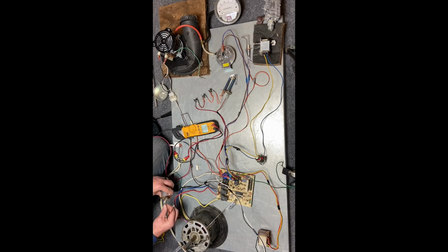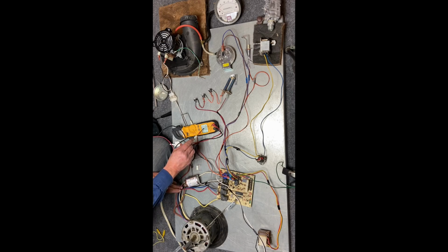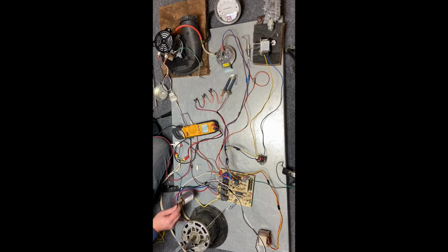We put the two wires back on. It's safe to touch now because we know it's discharged. Now you're going to hear people discharge a capacitor with a screwdriver. You want to be careful of that because if you're doing it with the screwdriver, if it's charged up, the electrons going from one side to the other can damage the capacitor. So when you're working with a capacitor, you want to make sure you discharge it with a 20,000 ohm 5-watt resistor or through your meter set to DC volts. So in this case, I prefer this because it's faster. Checked it, put the wires back on. We're ready to power the system back up.